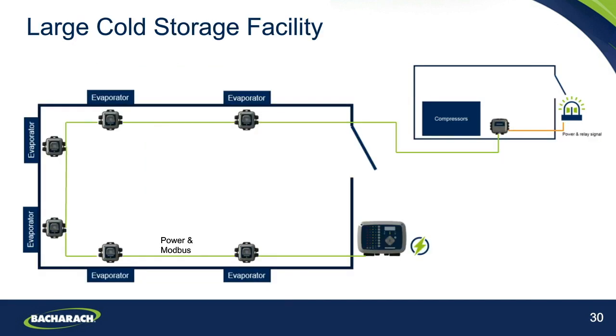And then, of course, we must remember large cold storage facilities as well. So if we've got a machinery room here driving a large facility, we typically expect to see a detector mounted in the return airflow of each evaporator within the room. And again, they can be daisy-chained with power and communications back to a centralized controller, and that can then run out to a machinery room as well. And we've got the AV alarms that we need outside the primary space through the gas detection controller, and we can use that additional horn strobe outside of the machinery room there. So, as I mentioned, this is not an exhaustive list.